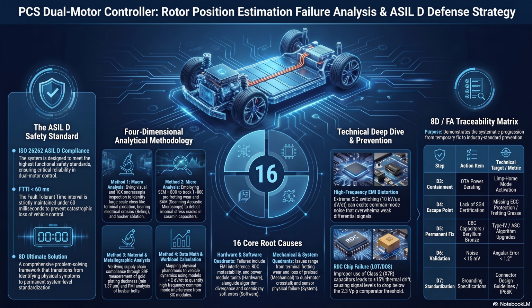Yes, fluting on the motor bearings. Fluting is such a fascinating diagnostic indicator because when investigators pull the steel bearings from the motor shaft, they often find this distinct, highly regular washboard-like wave pattern. Literally physically scarred right into the metal raceway. Exactly. It looks exactly like microscopic corrugated metal.